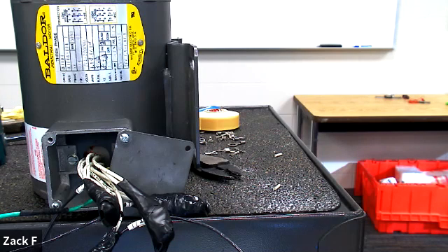Partially shorted, right? That means somehow, some way, remember those windings are stuck really close together inside that motor. Maybe this point is touching this point. You have a partially shorted set of windings there, so the resistance from here across that means less copper, less resistance.